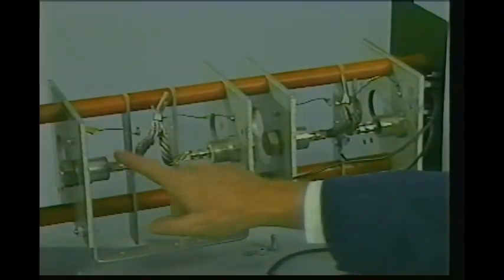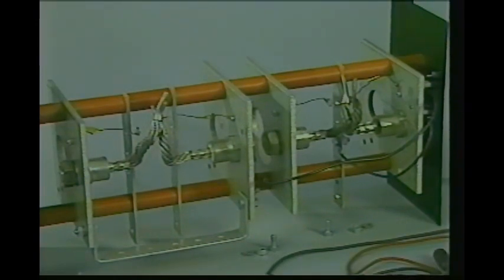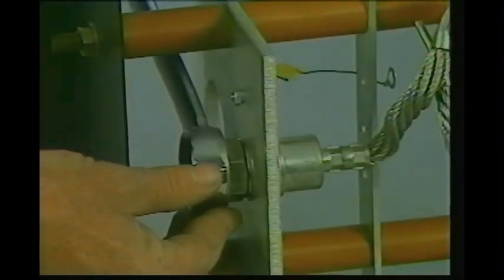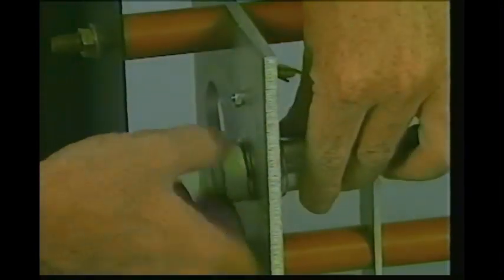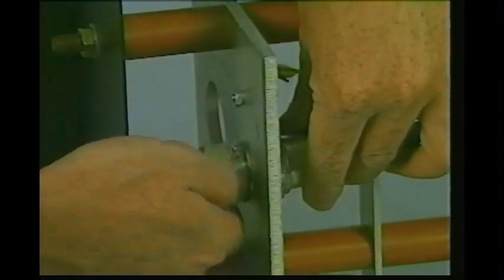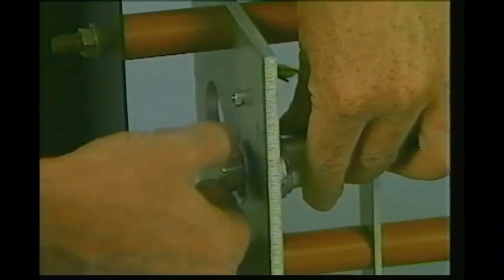The fourth diode is shorted and must be replaced. Remove the defective diode, check the part number, and obtain a replacement. If you cannot read the part number on the diode body refer to the service parts manual for the correct part number.